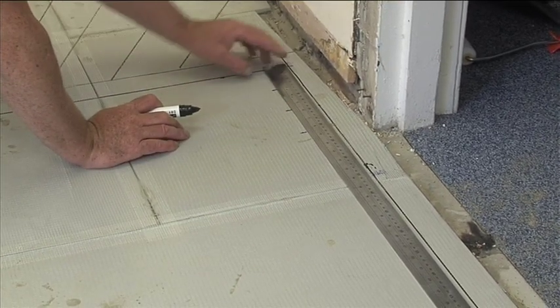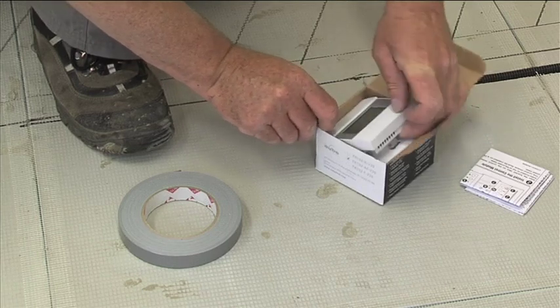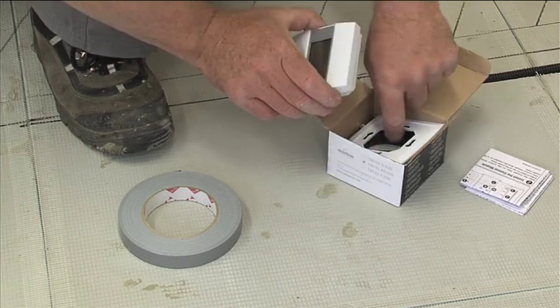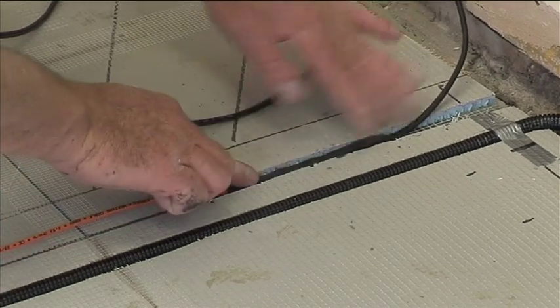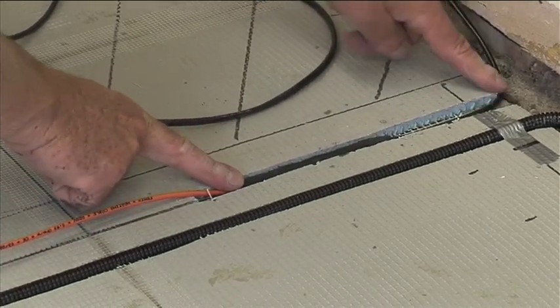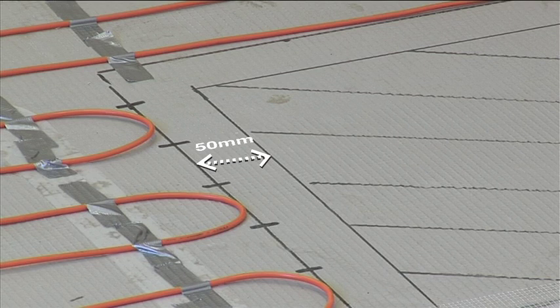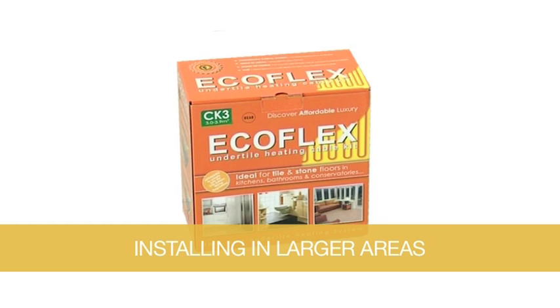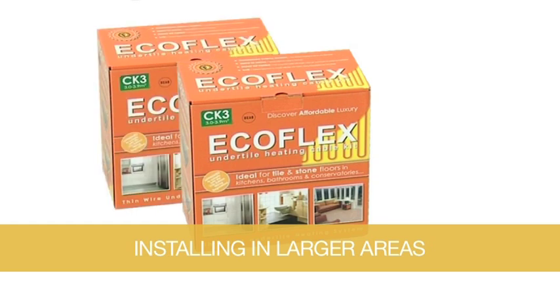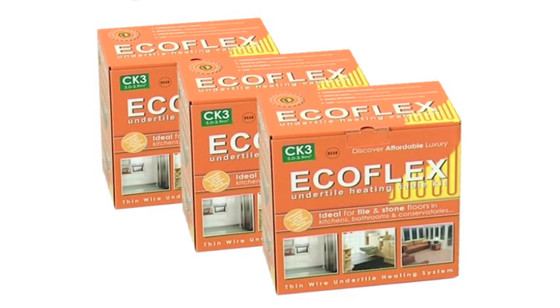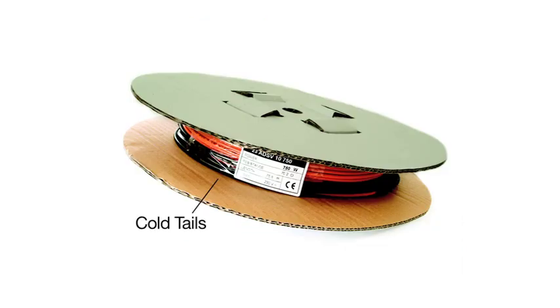Mark your cable start point. Ensure that this is close to the planned thermostat position. The ECOFLEX cable cold tail is 3 meters long. Cable spacing and perimeter wall clearance must be a minimum of 50 millimeters. A heating system for larger areas will require 2 or more heating cables. It is important to note that when installing multiple heating cables to take the following precautions.